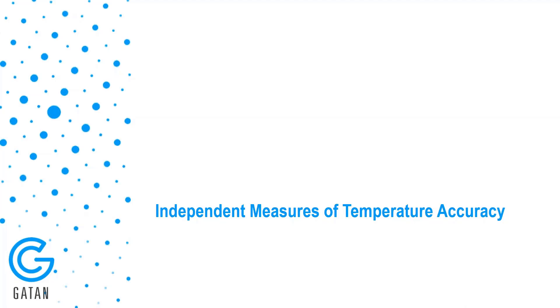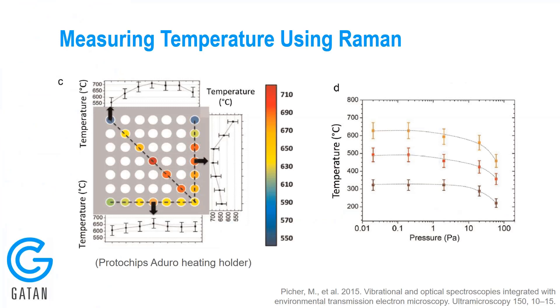Several groups around the world have published independent measurements of temperature accuracy. Here's an example using Raman spectroscopy — I want to preface that this is an older design of a Protochips holder, not their new technology, so the result is a bit outdated, but the technique is what I want to focus on. This was done at NIST, and they were able to use Raman spectroscopy inside the microscope to measure the temperature of a sample on the electron transparent windows, enabling quantitative measurement of temperature while the holder is inside the microscope.